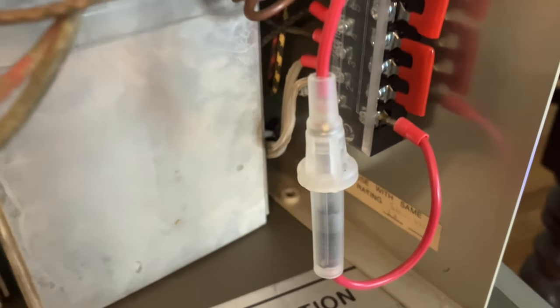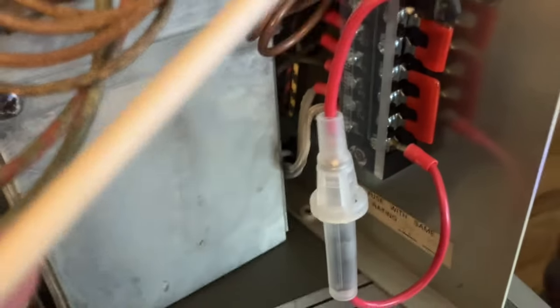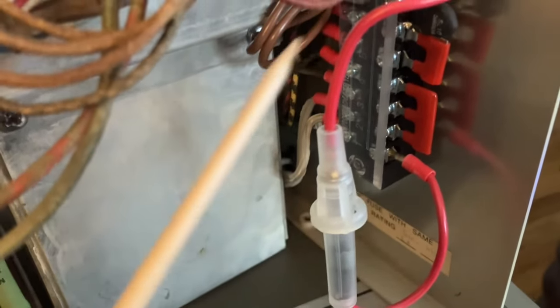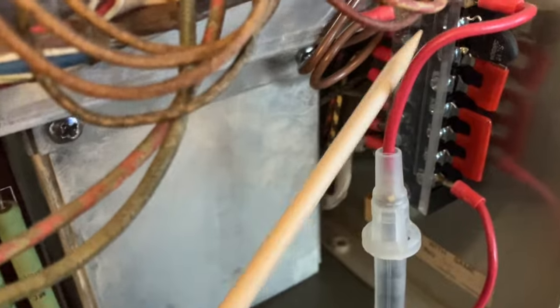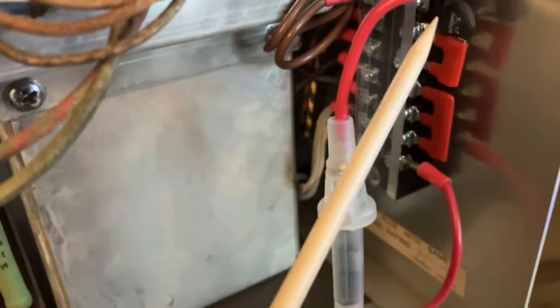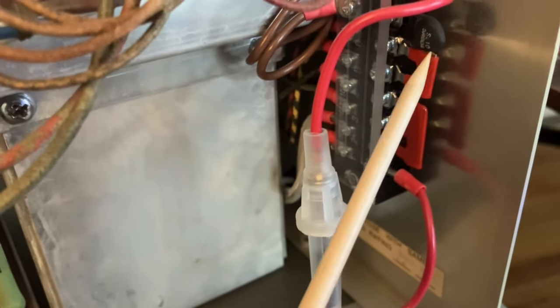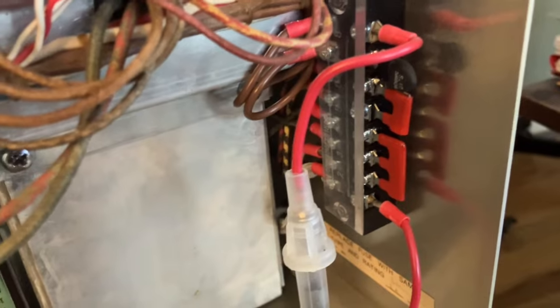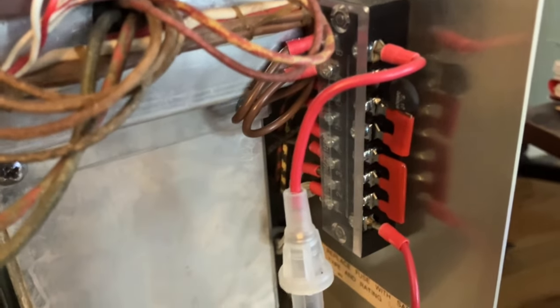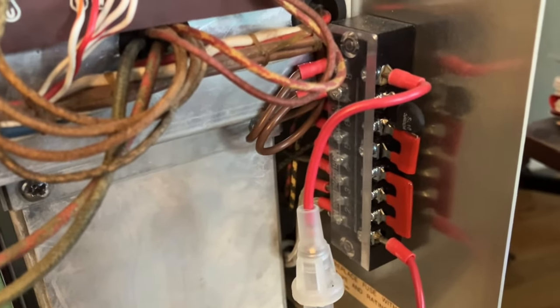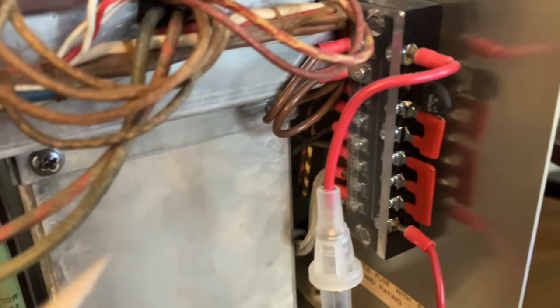I probably never will. Apart from that, from the fuse, it goes back out to the power switch connections, which are here, then comes back. It goes to a PTC, which limits inrush current, which is something I simply added for the heck of it since I had one. So this limits the inrush current into the scope, and in particular into the transformer and the CRT filament. Hopefully maybe prolong their life a little bit.